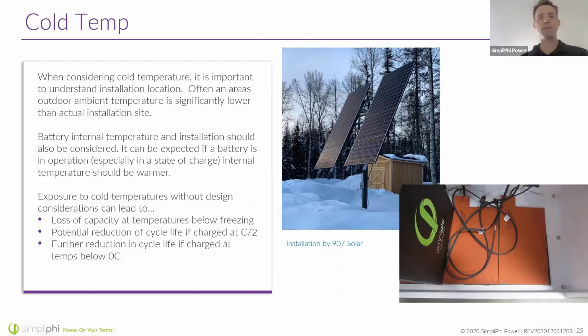So it's recommended not to be charging a battery. The batteries can discharge at lower temperatures, but not to be charging a battery at temperatures below 0 degrees Celsius. Now remember, that's the battery cell temperature we're talking about. And typically the battery cell temperatures are above ambient temperatures because batteries produce a little bit of heat as they charge and discharge. One solution for this, of course, is just to keep your batteries housed.